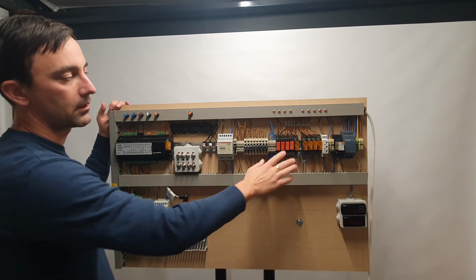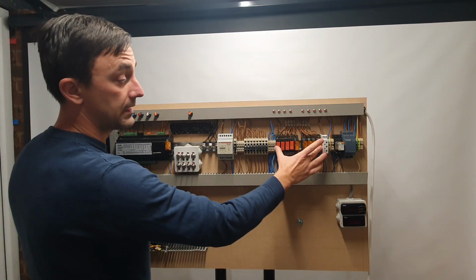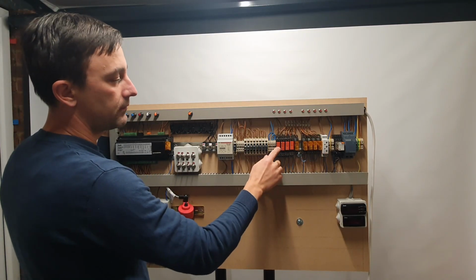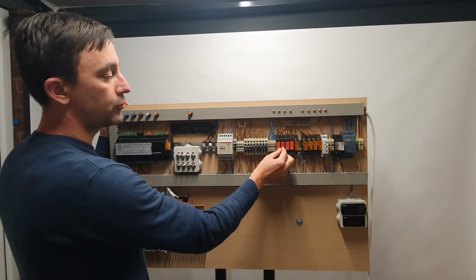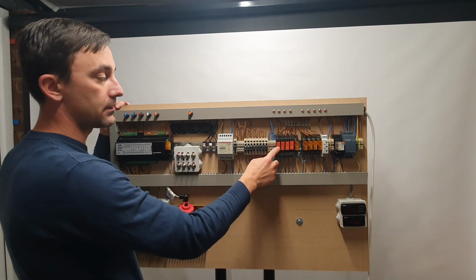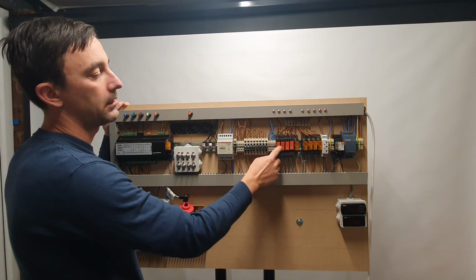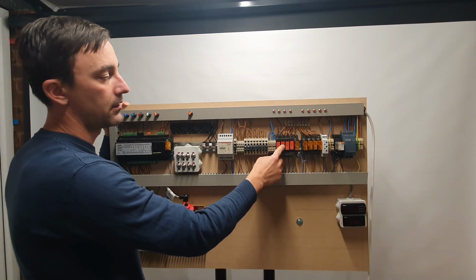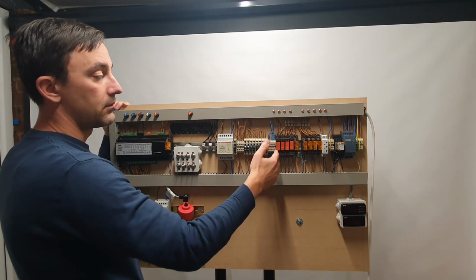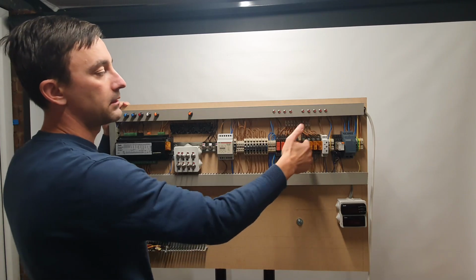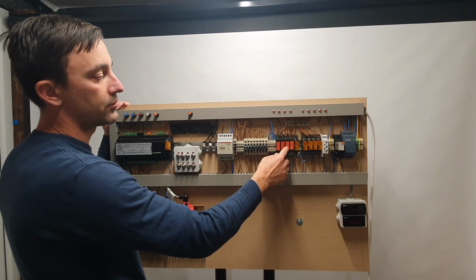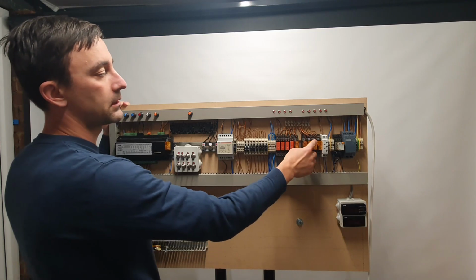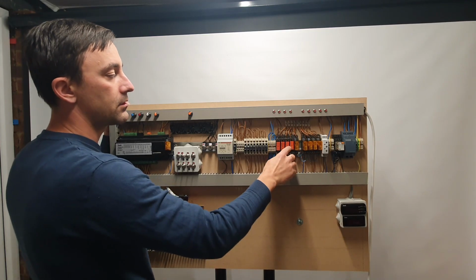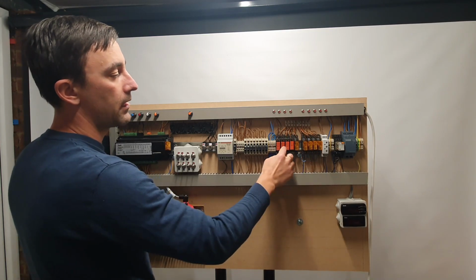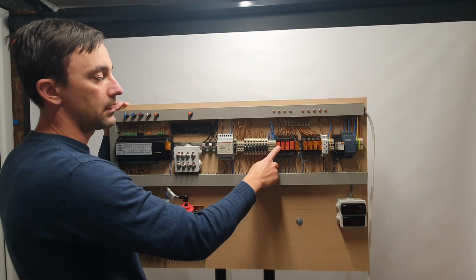Now you might count the relays and see I have 10, not 8. Compressor number 1 has 2 relays because one relay is a safety switch relay and the other one is just a compressor relay. But because it was too impractical for me to keep adding relays, I decided to use, for compressor number 2 up to compressor number 8, just a normal relay and bypass the safety relay.